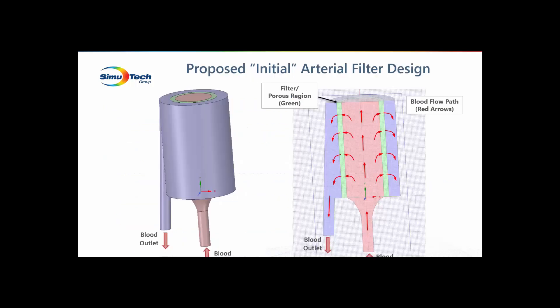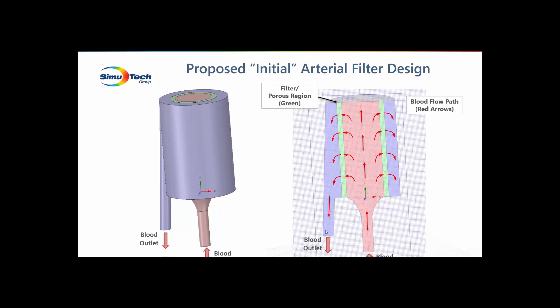For the initial configuration, we've chosen a cylindrical design. The model is composed of three sections. We have an inner section shown in red, the filter representing the porous media in the middle in green, and the outer region in blue which collects and returns the blood to the outlet port. The red arrows in the cross-sectional image on the right show the general direction of the blood as it passes through the device, coming in through the center, flowing out through the filter, and being collected and passing out through the blood outlet.